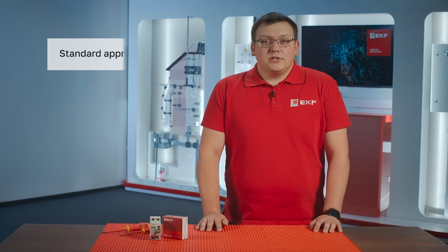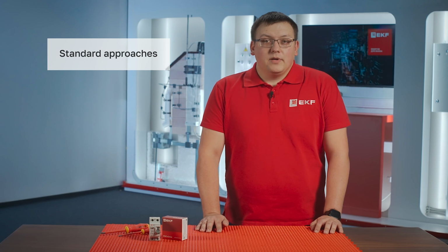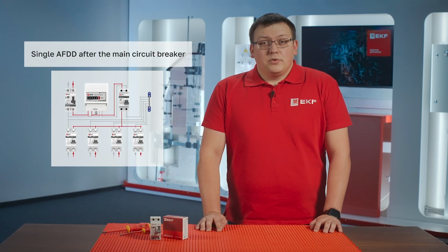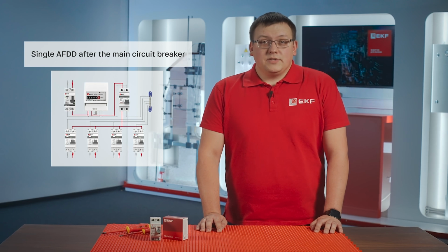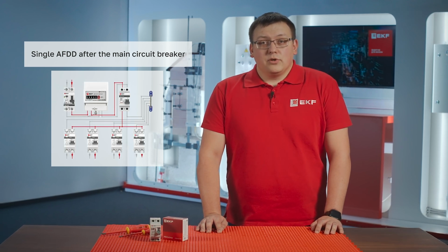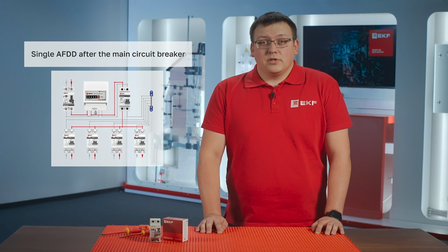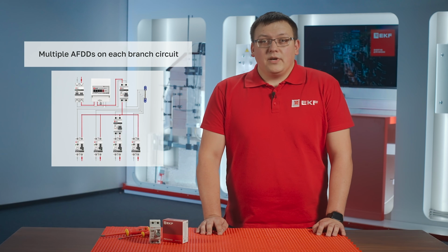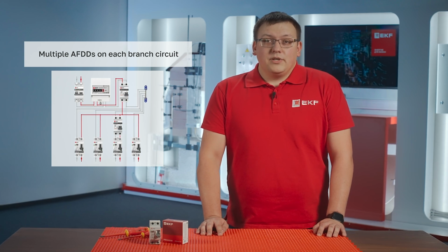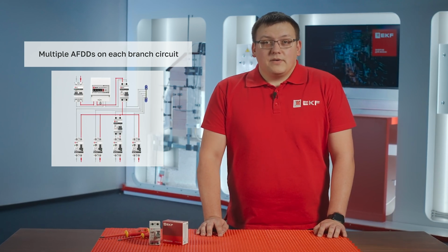There are different standard approaches to installing an AFDD, for example in a multi-unit apartment building, each with their pros and cons. First option is to install the AFDD after the main circuit breaker. The pro of this option is the relative affordability. The con: in the event of an arc fault, you would have to hunt it down across the entire apartment. Second option is to install AFDDs on branch circuits. Pros: it's easier to find the fault and the entire apartment won't lose power. Cons: it's expensive. To show how AFDD works, we'll build a modest test bench.